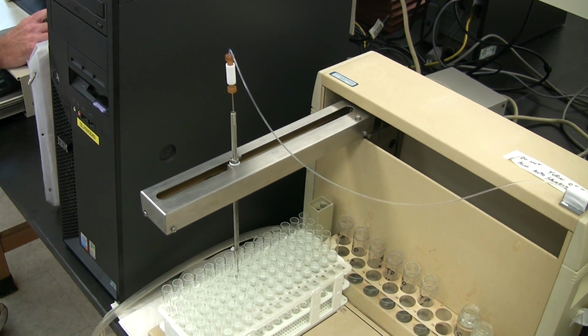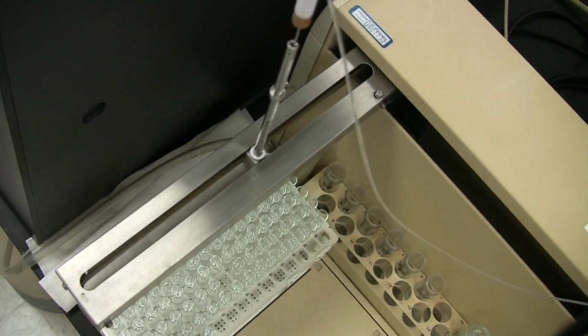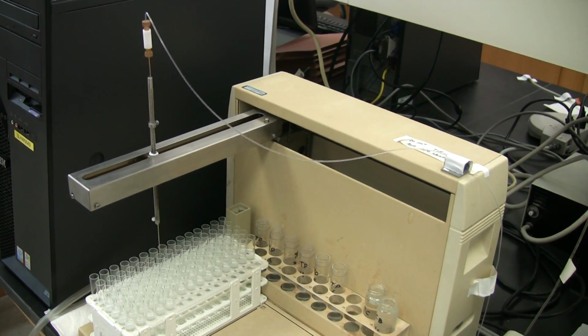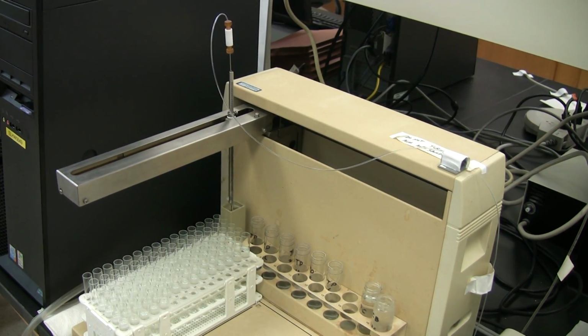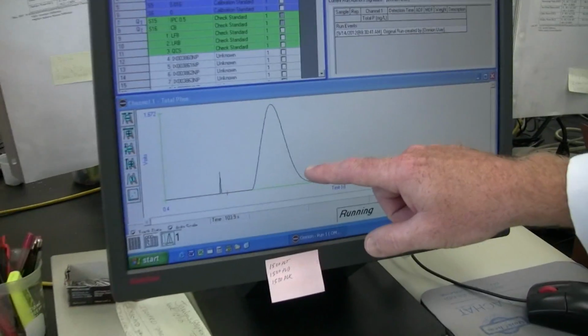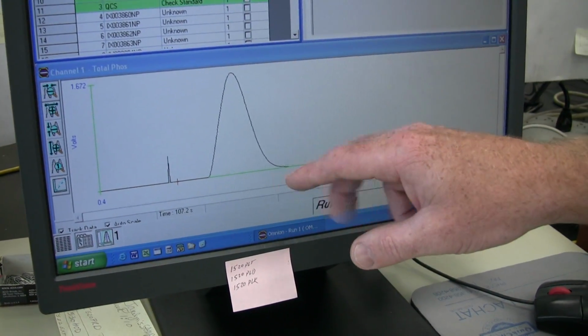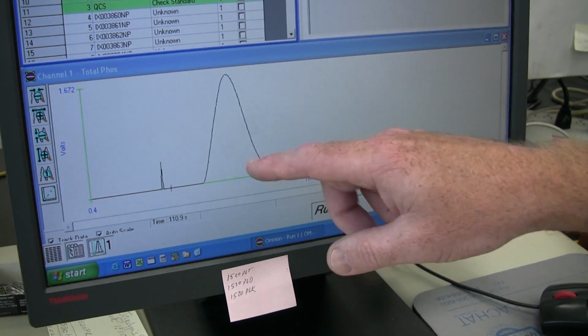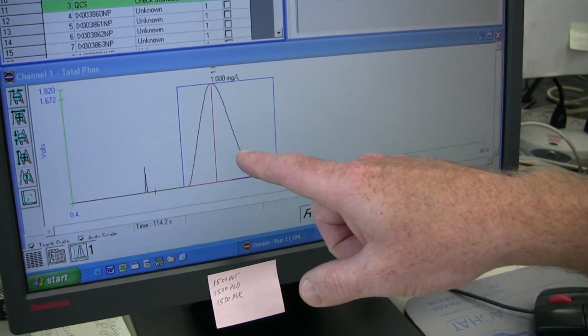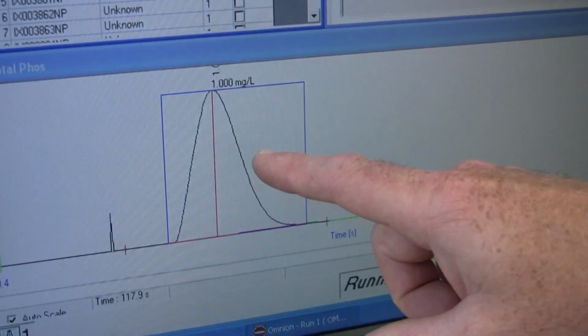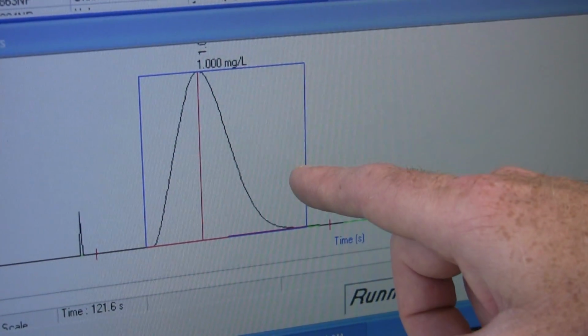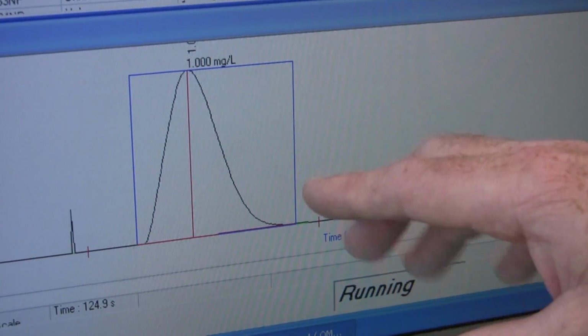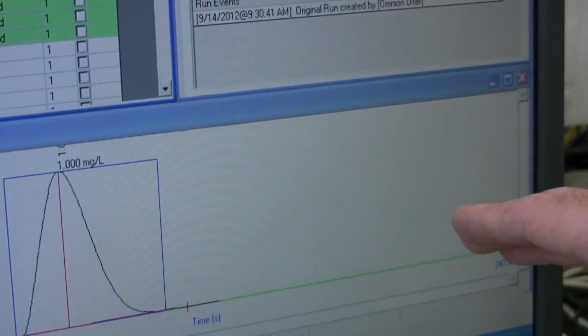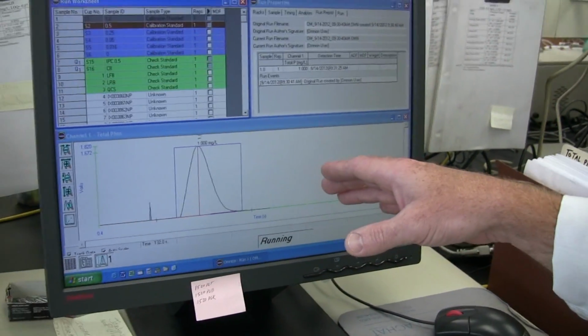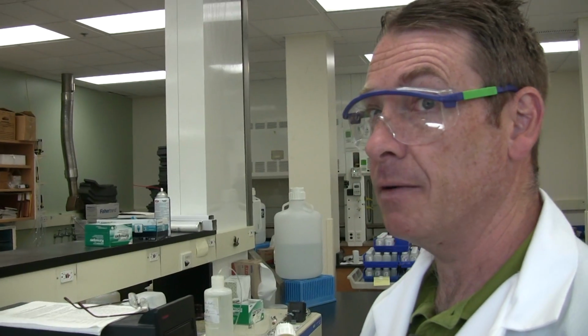The quality control that I have at the beginning of this run are a blank, a lab fortified blank, and a quality control standard that's another source of phosphorus, just to double check that my concentrations are correct. So this peak represents how much blue color basically is going past that detector. And what the instrument will do here is it'll figure out the peak area, which it just did, and it'll plot these peak areas in a standard curve to establish that calibration curve. And this is one of 6 standards that it will take to establish that curve, and once we get those 6 standards through the instrument, we can take a look at that curve. And our basic criteria for that curve is it has to have an R of 0.995 or better, that it is linear. And we can look at that in a few minutes once that is done.